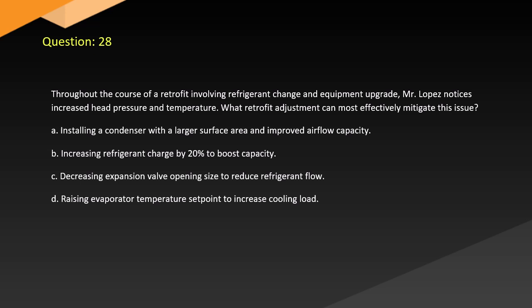Question 28. Throughout the course of a retrofit involving refrigerant change and equipment upgrade, Mr. Lopez notices increased head pressure and temperature. What retrofit adjustment can most effectively mitigate this issue? A. Installing a condenser with a larger surface area and improved airflow capacity. B. Increasing refrigerant charge by 20% to boost capacity. C. Decreasing expansion valve opening size to reduce refrigerant flow. D. Raising evaporator temperature set point to increase cooling load.